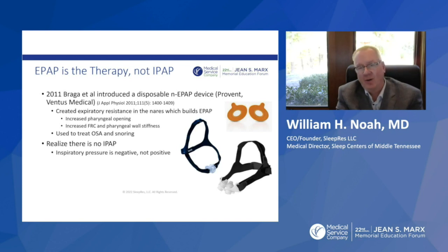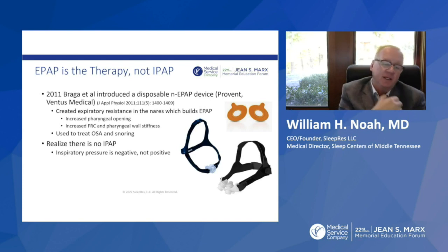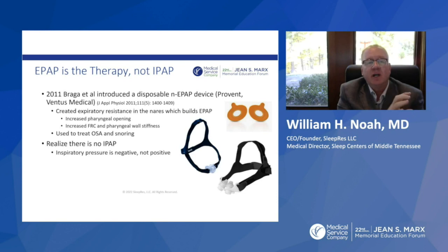It's very hard to tolerate because you have this huge change of breathing with negative inspiratory and then blowing out against that positive expiratory. And because it's flow dependent, in other words, the more the flow, the higher the EPAP, you get most of the resistance in the very beginning of exhalation when you're trying to get your air out. But at the end of exhalation, which is most critical, there's no flow. So therefore, there's no EPAP. And that's why they can only treat mild cases, because there's no end-expiratory pressure. And the fact that they're difficult to get used to.